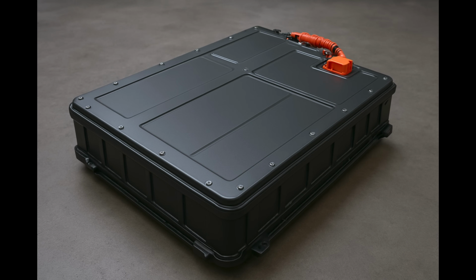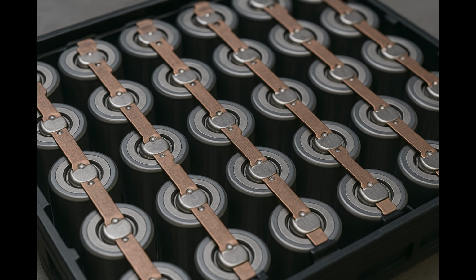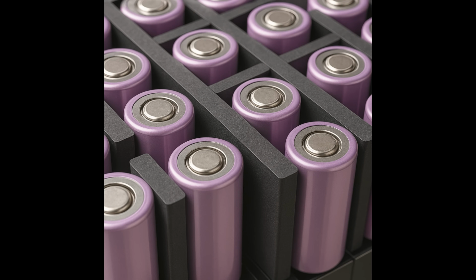Another is mechanical protection. Robust cell packaging and cushioning to minimize mechanical damage, and reinforced battery enclosure designs to withstand impacts or crush forces. You should also implement electrical protections, including incorporating reliable fusing or circuit interrupters to prevent overcurrent. You should also use charge and discharge limiters to avoid electrical abuse conditions. Another critical aspect is cell spacing in your pack or module design, including physically separating cells or incorporating thermal barriers to prevent heat propagation between cells.